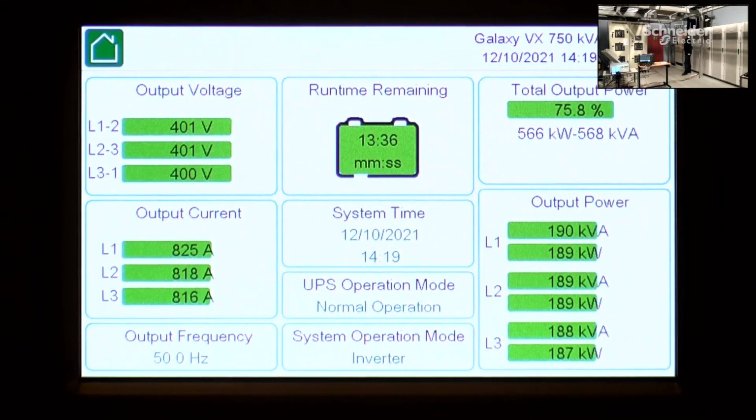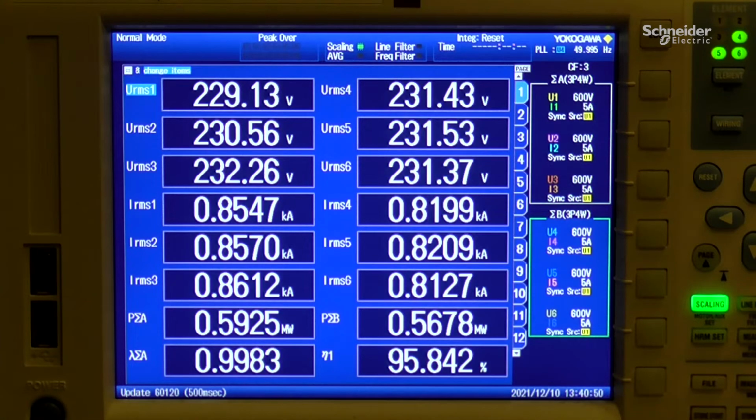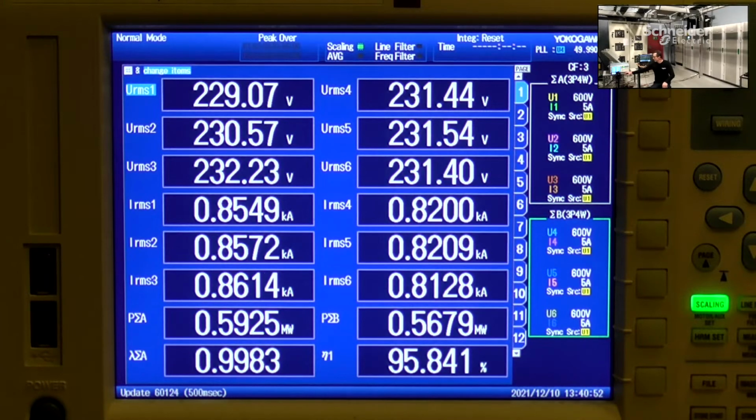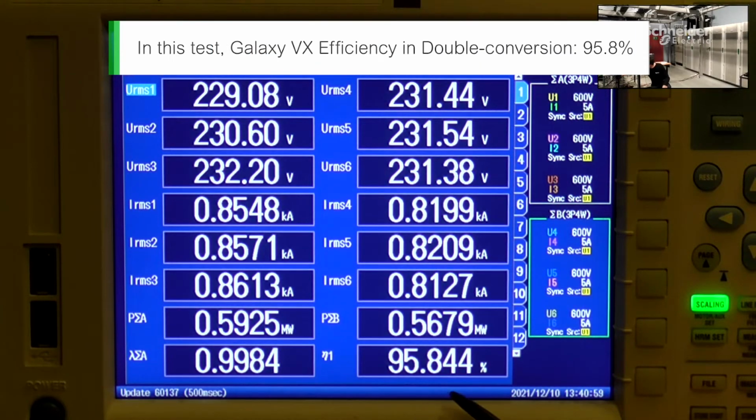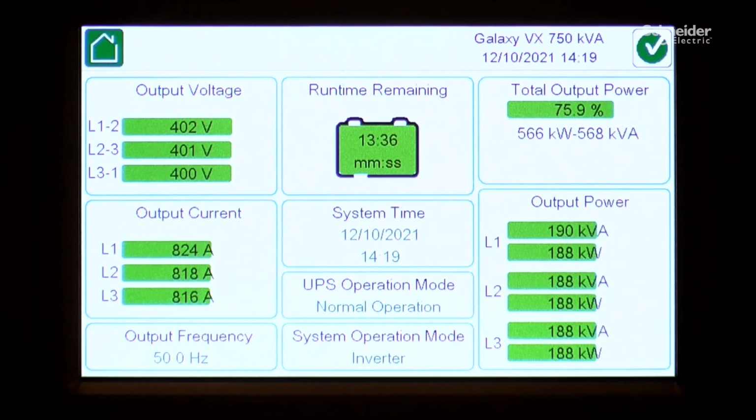Now, I'm going to go back to my power analyzer and I'll show you on my power analyzer that the efficiency when we have around 75% load is 95.84. So almost 96%.